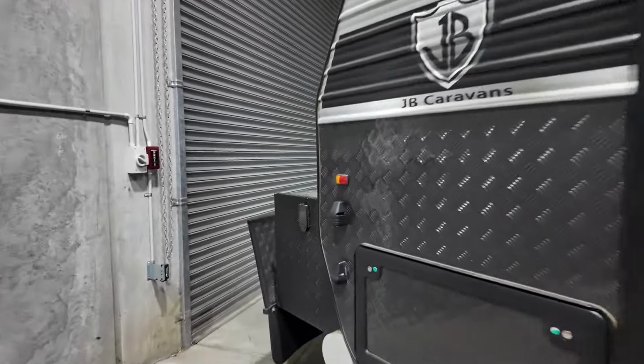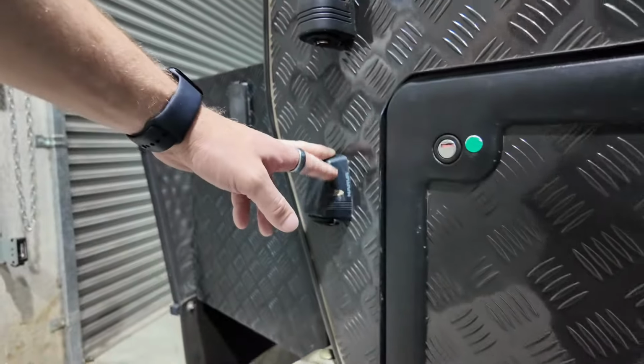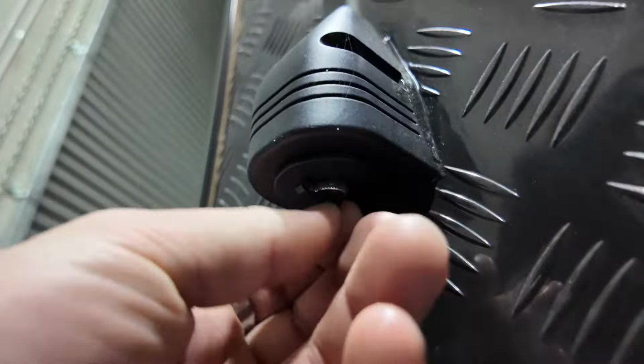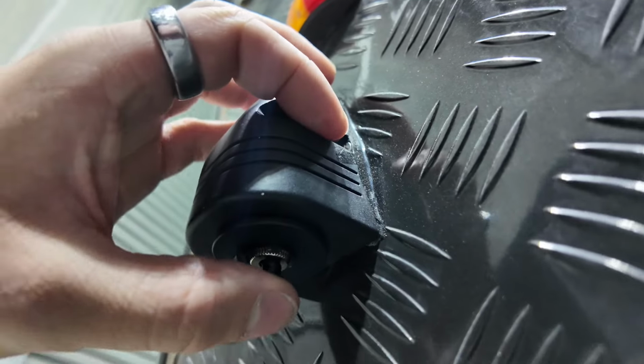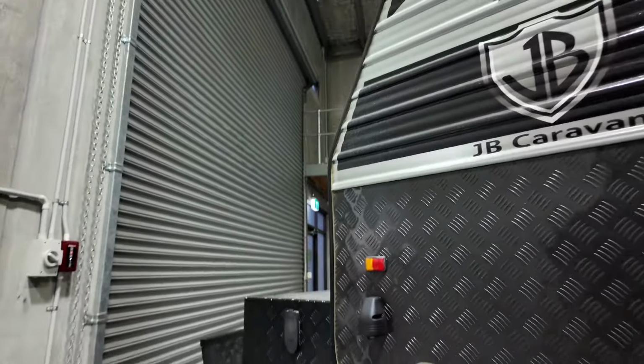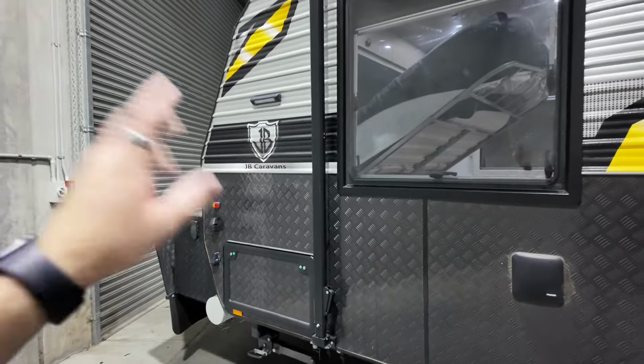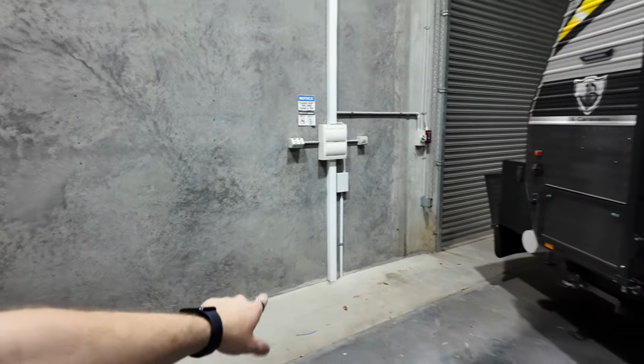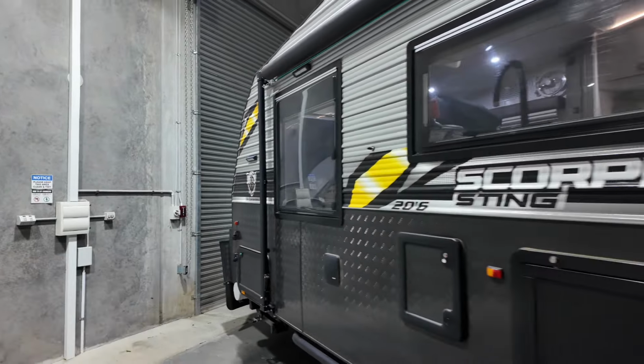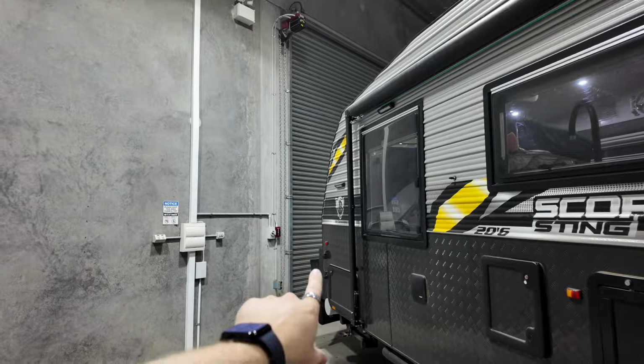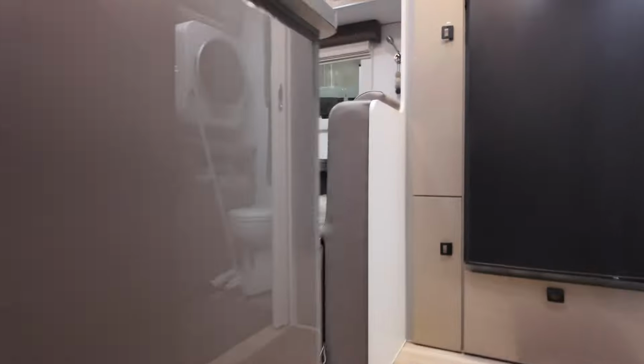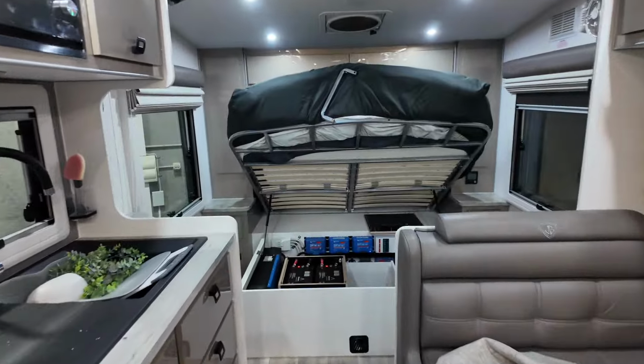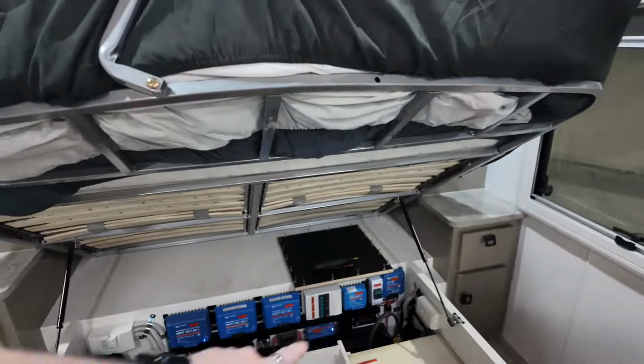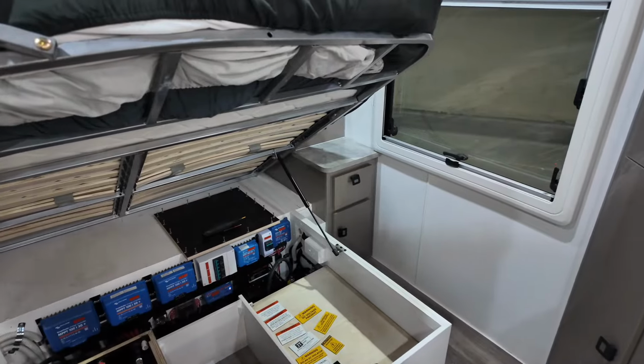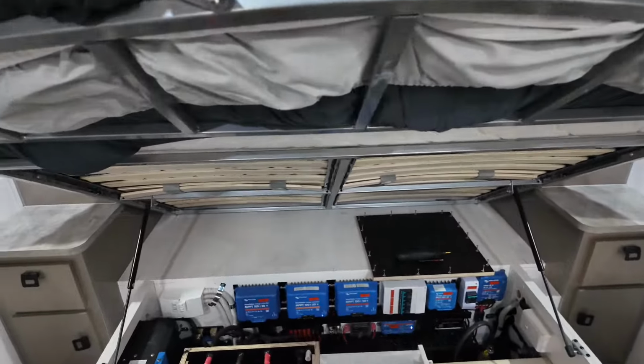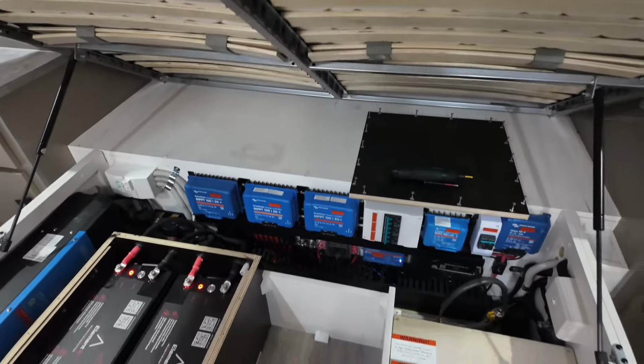On the outside of the van they had an original cigarette socket. This has got nothing to do with what we've done, but we've installed a female output. So all the customer has to do is buy the Starlink Mini kit, get the dish with the 15-meter cable that comes with it, and plug it in. There's no switch on that circuit, so plugging it in is essentially switching it. That 15 or 20 meter lead that comes with the Starlink Mini will be at 30 volts from the converter. We've got a 12 volt input to the converter through the fuse panel, and we've hardwired the output to that unit, so 30 volts, which is perfect for the Mini.